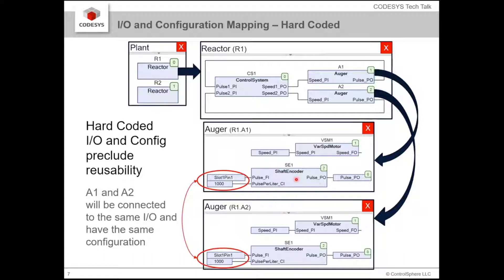The shaft encoder needs to get pulses from the shaft encoder and it also has to have a scaling factor — depending on how many pulses per liter of material being augered out or something along those lines. So we need to connect it to an IO point and we have to give it a configuration. In the old days we just hard-code that variable, that global variable, hard-code some parameter, and we'd be done.